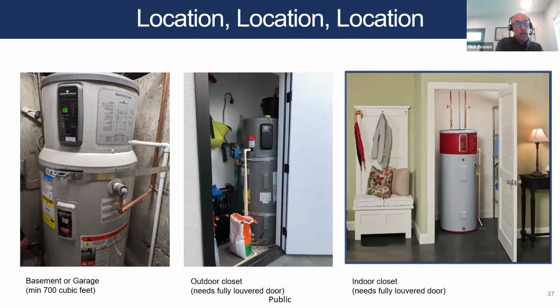So basements and garages are good spaces because they've got a lot of area to draw air from. Outdoor closets are good, but not this picture in the middle. This was a client of mine that put it in here and didn't give it enough airflow. That door should have been fully louvered, and they had all kinds of trouble with it until I helped them correct it. And now it's fine. Indoor closets work too. Again, fully louvered door. Or you can duct the inlet and the outlet to outside if you prefer.